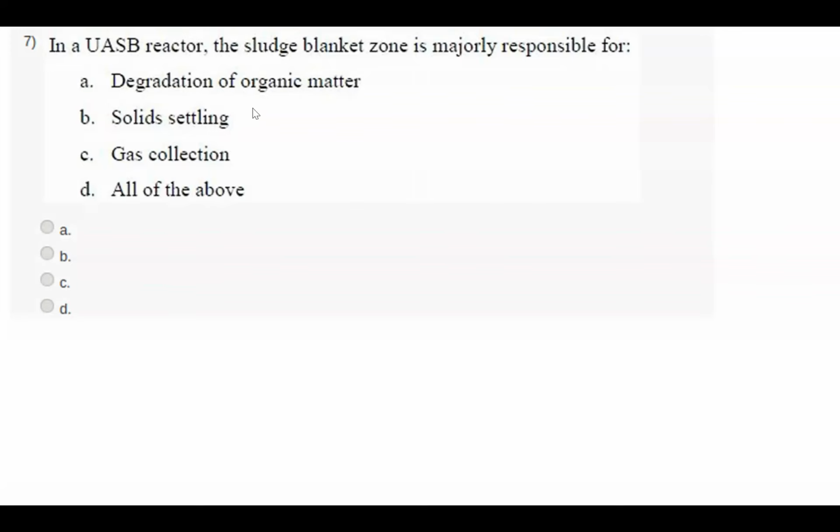Even the blanket serves as a media for the whole operation. After the processing, the microorganisms will be there, even in the sludge above the blanket. When the sludge becomes flocculent and its mass becomes higher, then because of gravity it will come down, but we are also providing the inflow, so the force is going up. Got it? Is it confusing?